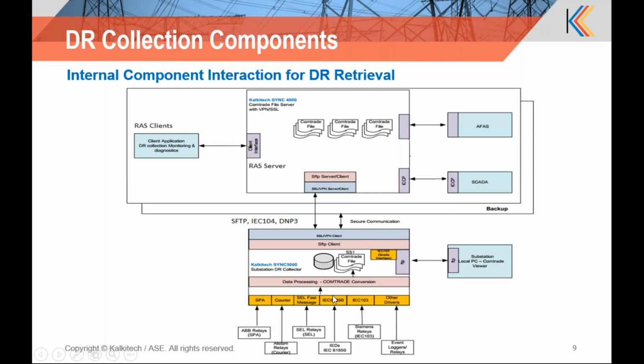This will be converted onto the ComTrade file, that is IEEE standard, and these files are available onto the system, and this file will be pushed to the central system using a TLS 1.2 tunnel between the substations and central system.